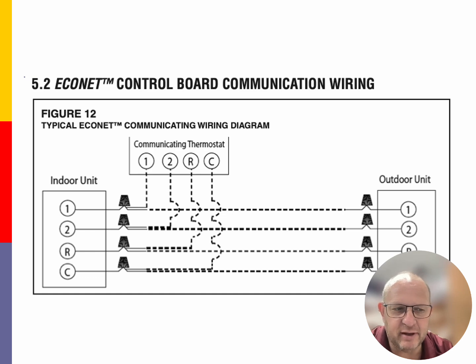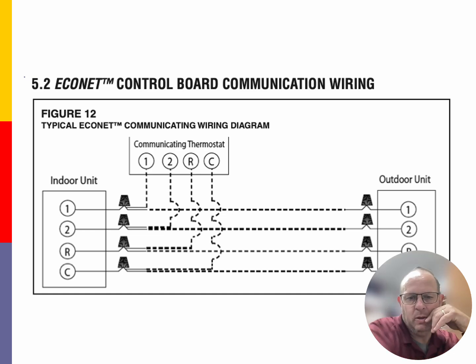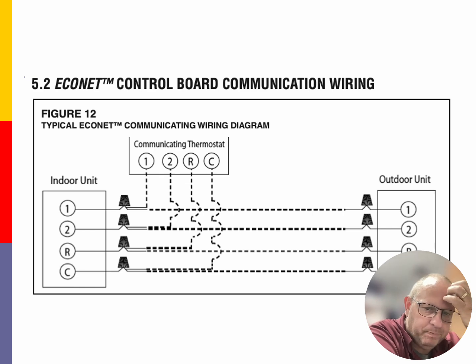If they need to go faster, the compressor will ramp up and go faster. If we need to provide more heat, the furnace will ramp up and provide more heat. If we need to slow down really far, we can do that, and the system will work just fine. So hook these terminals up exactly like they are listed. R and C are the power wires, 1 and 2 are the communicating wires. And there's a lot of things that we can do with these systems, a lot of systems that we can run very, very well.